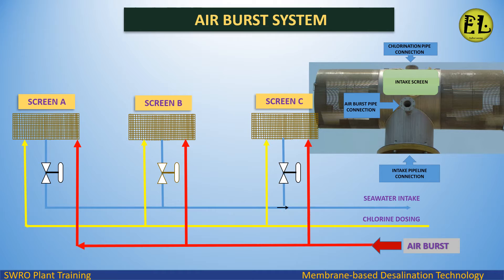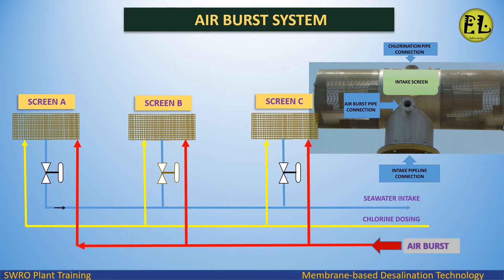Screens are made of copper and nickel alloy wedge wires with a clearance of about 3 mm. Both ends of the screens can be opened by hinged covers for cleaning purposes, also from inside. The screens have connections for chlorination and airburst.